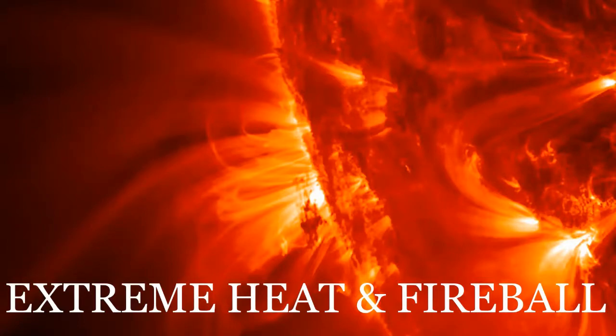It's also accompanied by a fireball. What's interesting, and we'll get into this later with the PPE and arc rated clothing, is you're really dealing with 2 hazards in one. If you took the fireball out of the picture, the person would still be burned, almost like getting a sunburn, probably the worst one you've ever had. And on top of that there's a fireball. So you get a really bad sunburn and you've been lit on fire if you're not wearing the right clothing.